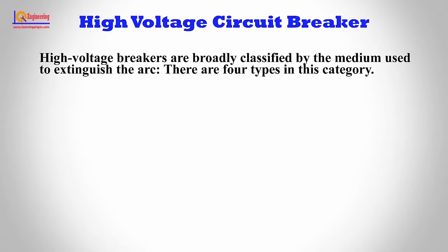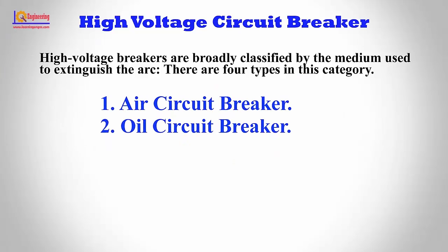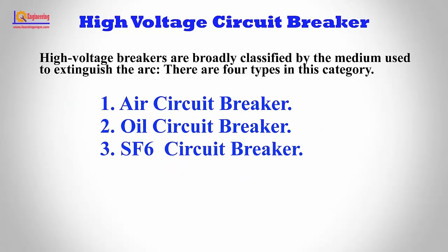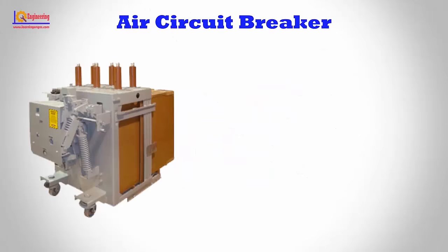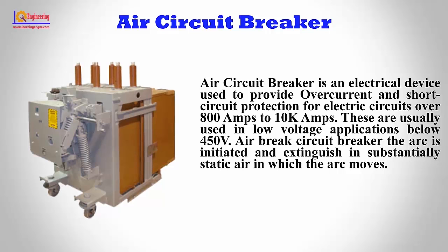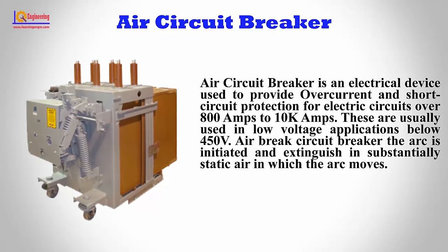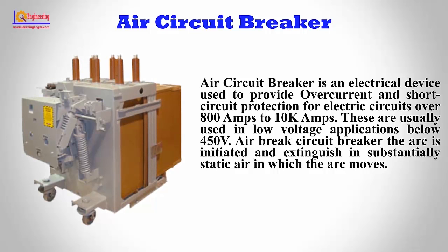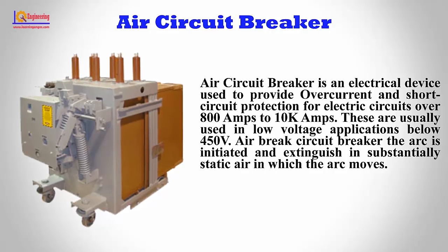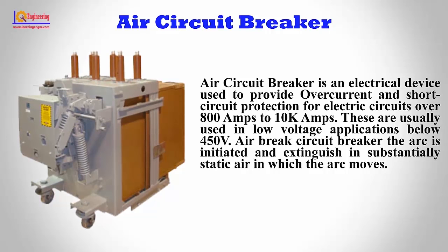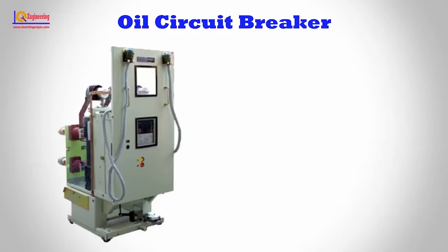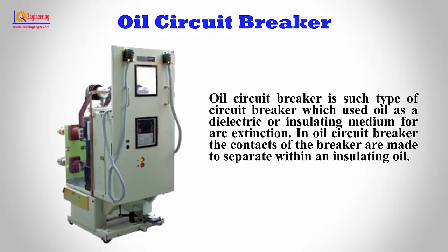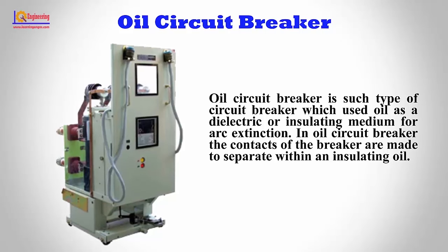High voltage breakers are broadly classified by the medium used to extinguish the arc. High voltage breakers are typically used to provide overcurrent and short circuit protection for electric circuits over 800 A to 10 kA. Air break circuit breakers use substantially static air in which the arc is initiated and extinguished as the arc moves. Oil Circuit Breakers use oil as a dielectric or insulating medium for arc extinction.